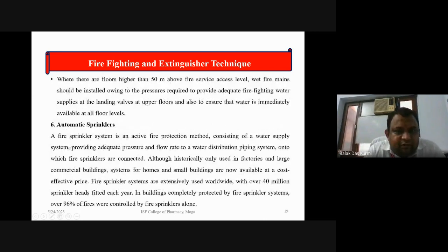Where there are floors higher than 50 meters above fire service access level, wet risers should be installed to provide adequate firefighting water supply at the landing valve at upper floors, and also to ensure that water is immediately available at all floor levels. And the next is automatic sprinklers.